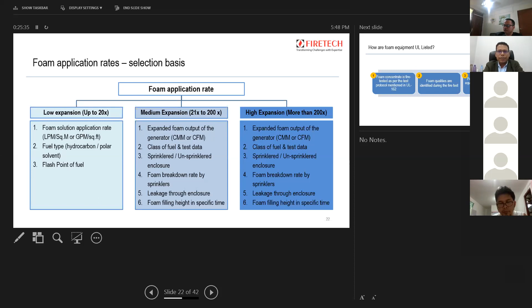High expansion foam systems are almost similar to medium expansion. The only difference is the expansion value is higher, so high expansion foam systems fill the enclosure at a much faster rate. And here also the first factor is the foam output from the generator, then the class of fuel and the test data. Again, whether the building is provided with sprinklers or it is an unsprinklered enclosure. Then the foam breakdown rate by sprinklers, then the leakage through enclosures, and the foam filling height in a specific time. So if you see, the medium and the high expansion foam systems are almost similar. What varies is only the expansion value. So the design approach remains the same, but the foam filling height changes due to the change in the expansion ratio.